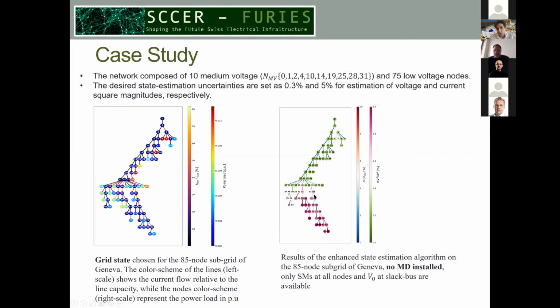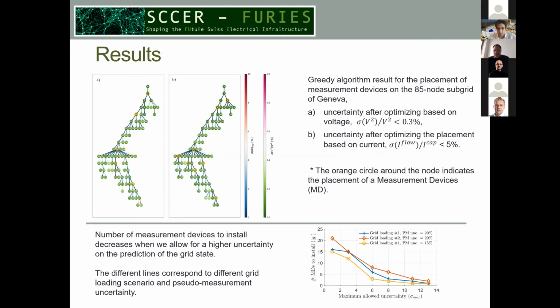Down there in the LV network, we are in the red regions. The desired values of state estimation error are 0.3% for voltage estimation and 5% for power flow or current estimation, which cannot be achieved using only smart meter data.